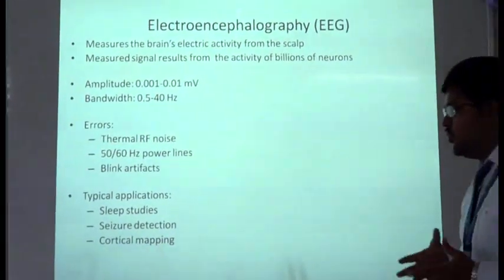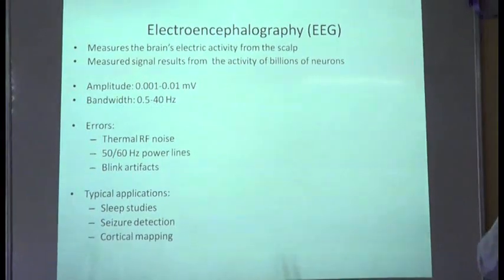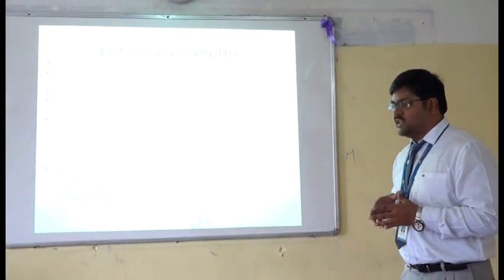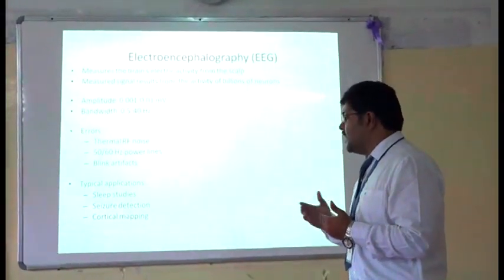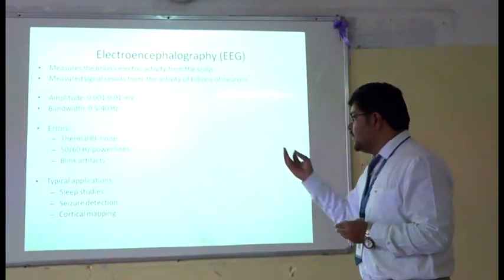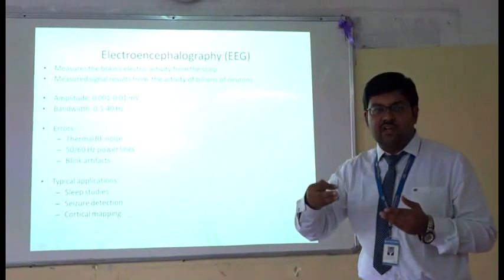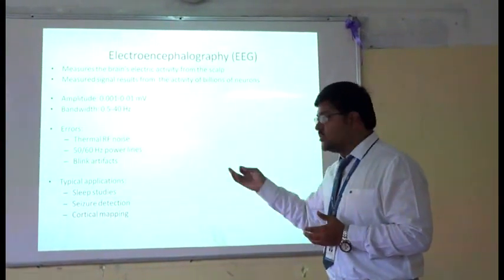Next is the Electroencephalogram, also called EEG, which is the measurement of the brain's electrical activity from the scalp. The measured signal results from the activity of billions of neurons. Its amplitude is between 0.001 to 0.01 millivolt, and its bandwidth is between 0.5 to 40 Hz. Noise sources in EEG include thermal RF noise due to heating of the electrodes or the EEG system, electrical interference noise at 50 to 60 Hz, and blink artifacts caused when the patient blinks during recording.